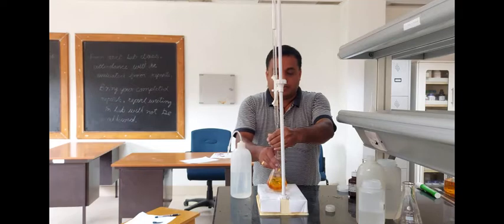We are adding sulfuric acid continuously, and the final color is not coming, which means there is a high alkalinity value for the synthetic water.